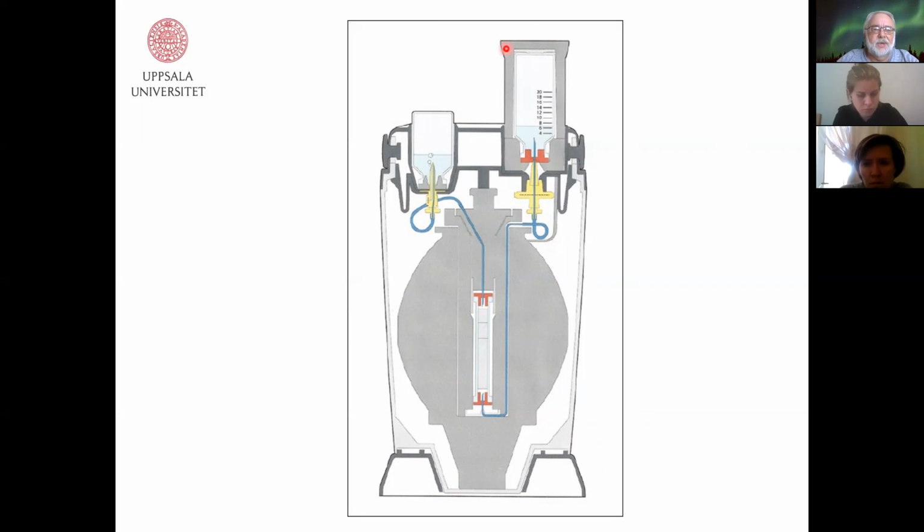So typically generator construction contains a needle, well, some bacterial filter in one needle. You put the reservoir with saline, and on the other needle, you place a vacuum vial. So under-pressure sucks in saline from the eluent vial.